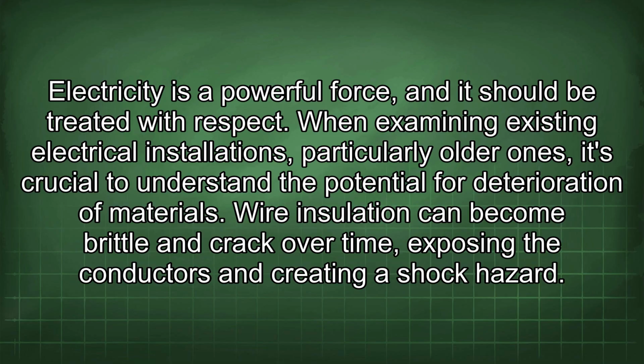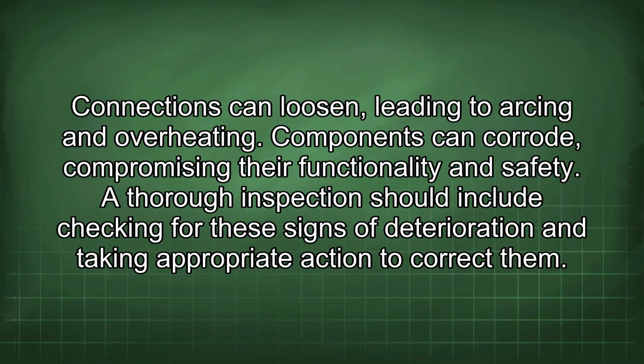When examining existing electrical installations, particularly older ones, it's crucial to understand the potential for deterioration of materials. Wire insulation can become brittle and crack over time, exposing the conductors and creating a shock hazard. Connections can loosen, leading to arcing and overheating. Components can corrode, compromising their functionality and safety. A thorough inspection should include checking for these signs of deterioration and taking appropriate action to correct them.